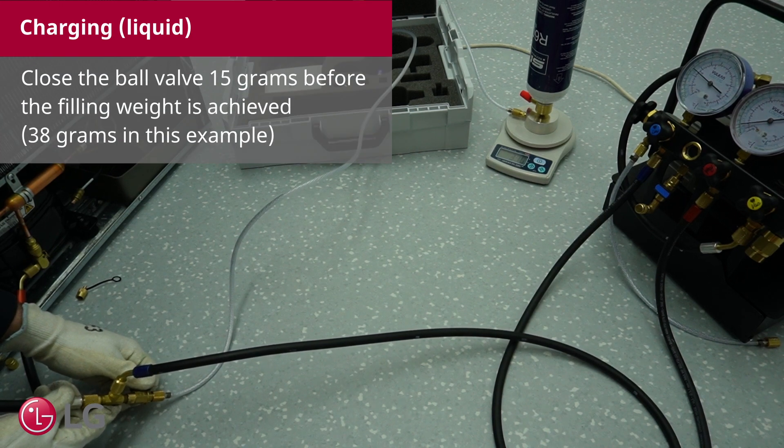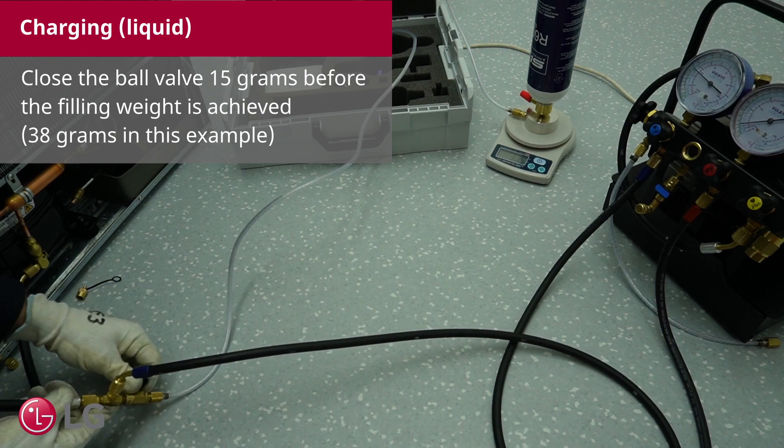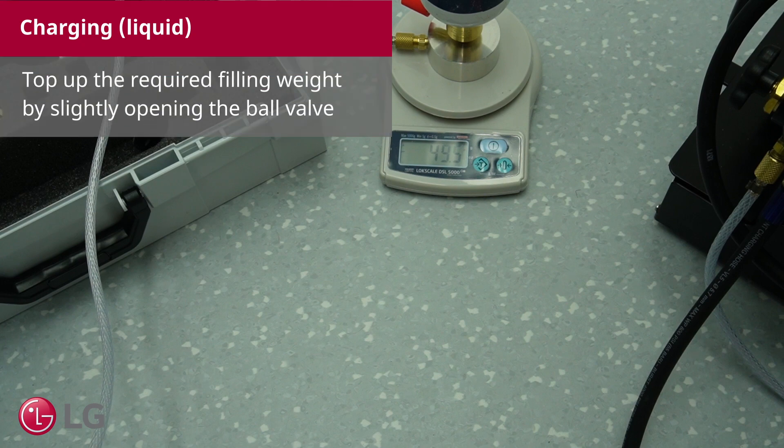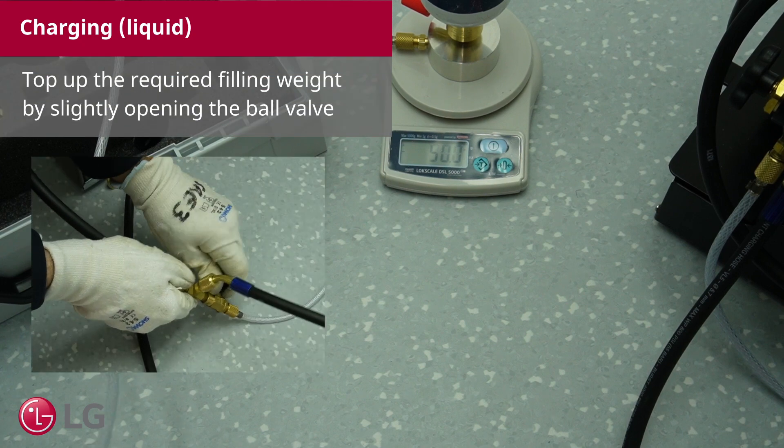Close the ball valve 15 grams before the filling weight is achieved, 38 grams in this example. Top up the required filling weight by slightly opening the ball valve.